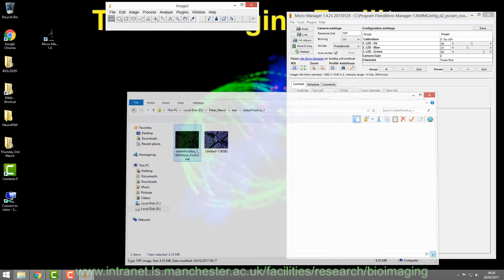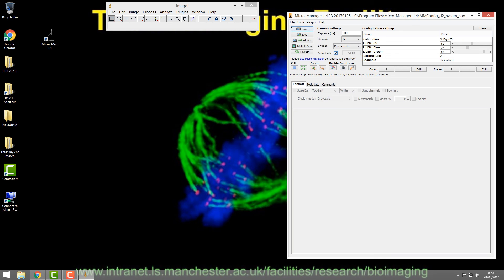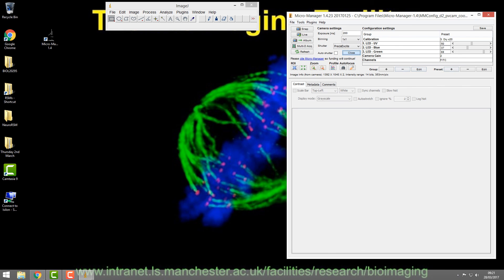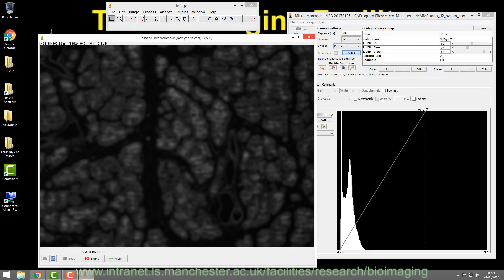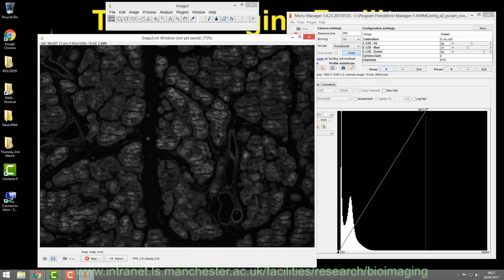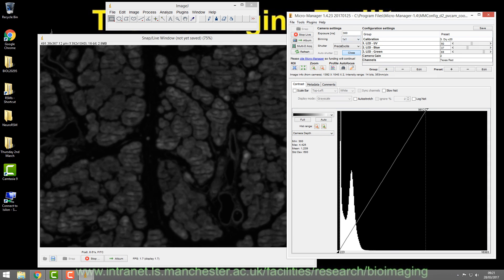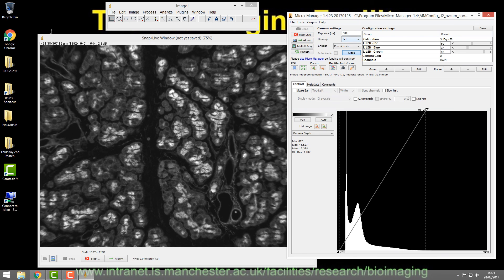To take manual control back from the PC, untick Auto Shutter — you can now open and close the shutter manually. Push the bar in, find your next sample, go back to whichever channel you want to look at, open the shutter, and move to another area. Pull the bar out, go live, and focus on your image. You don't need to change the exposure times — these should stay consistent between different areas of your slide.